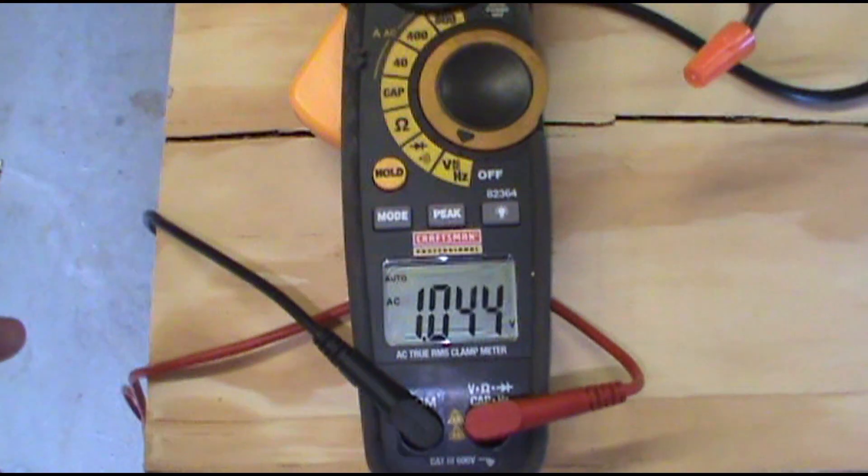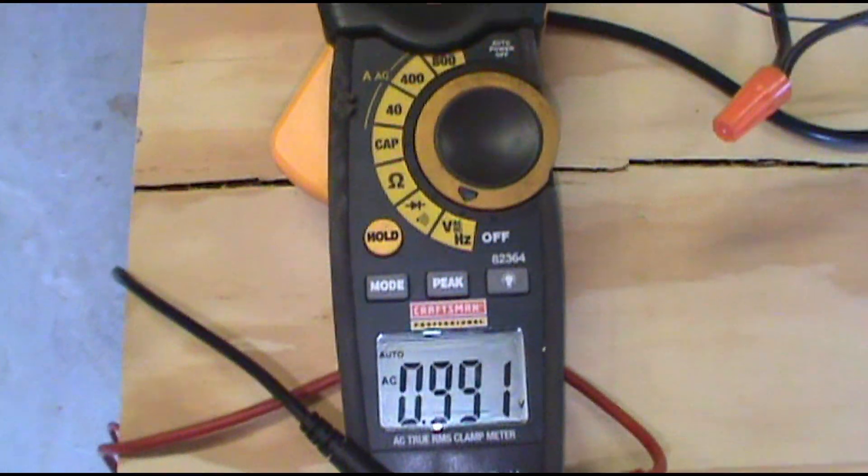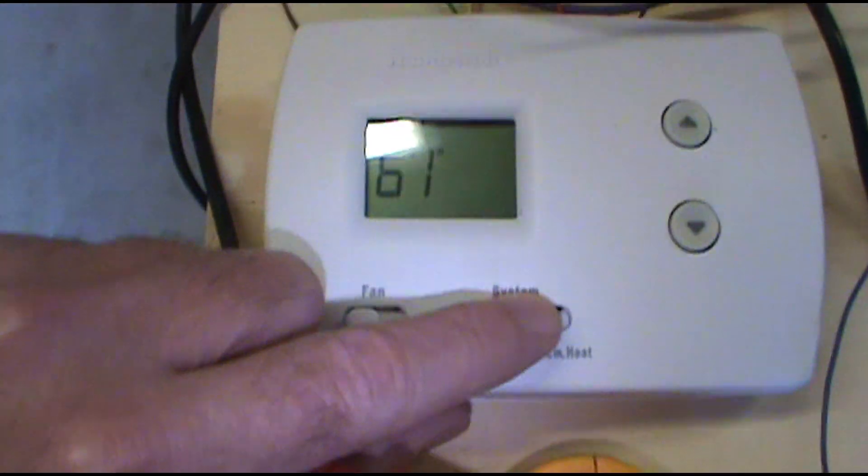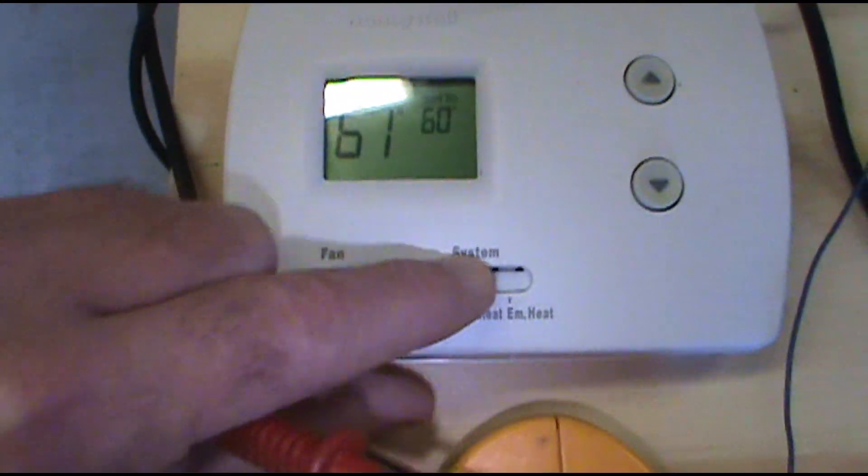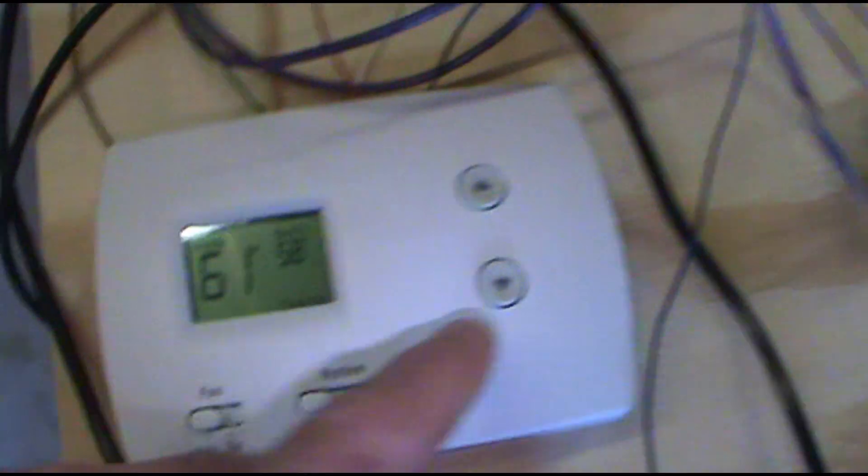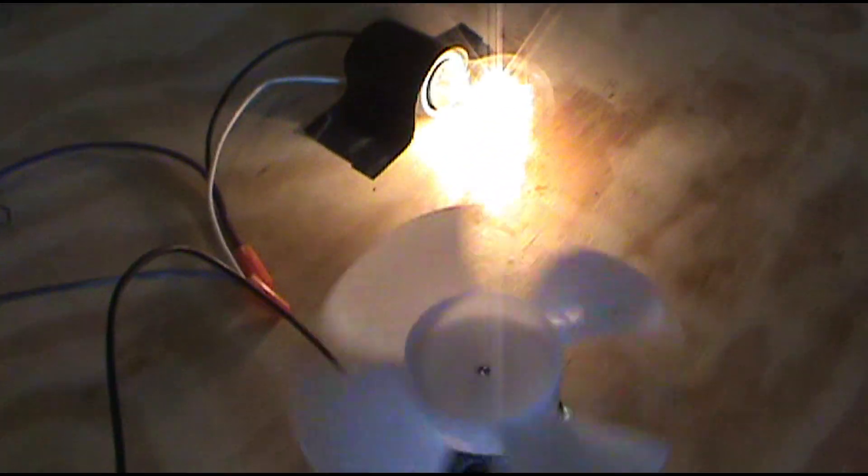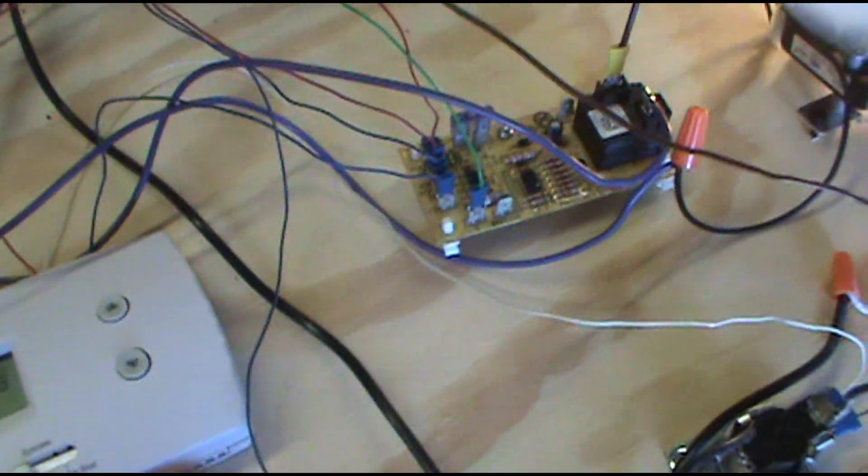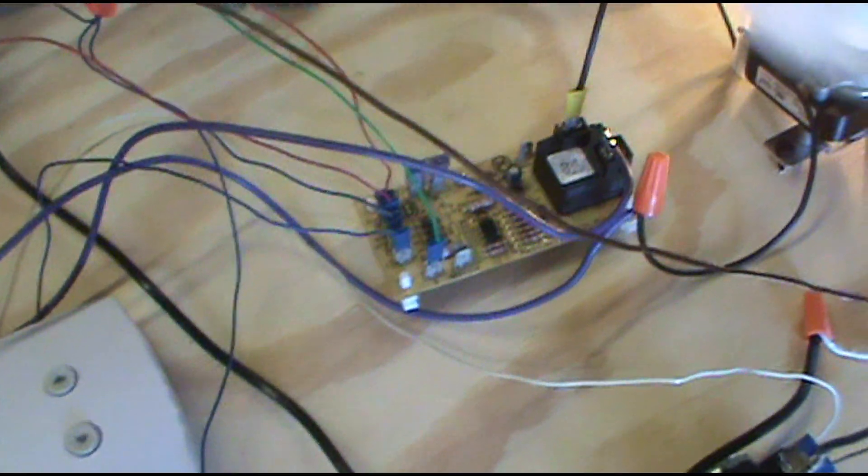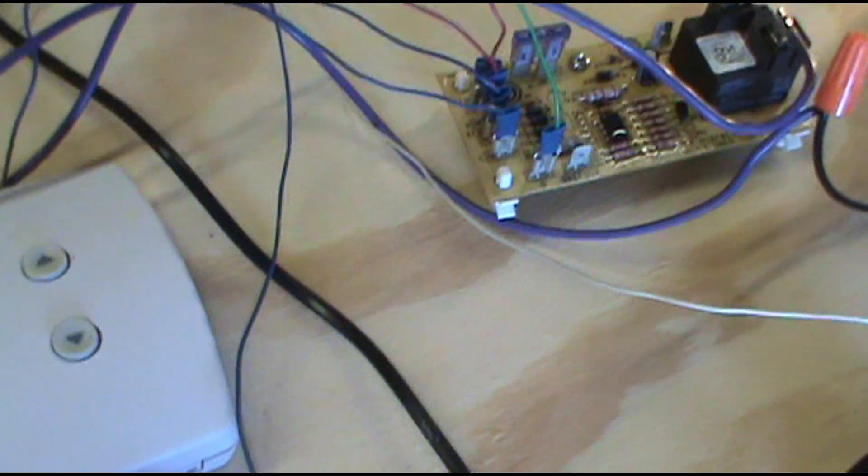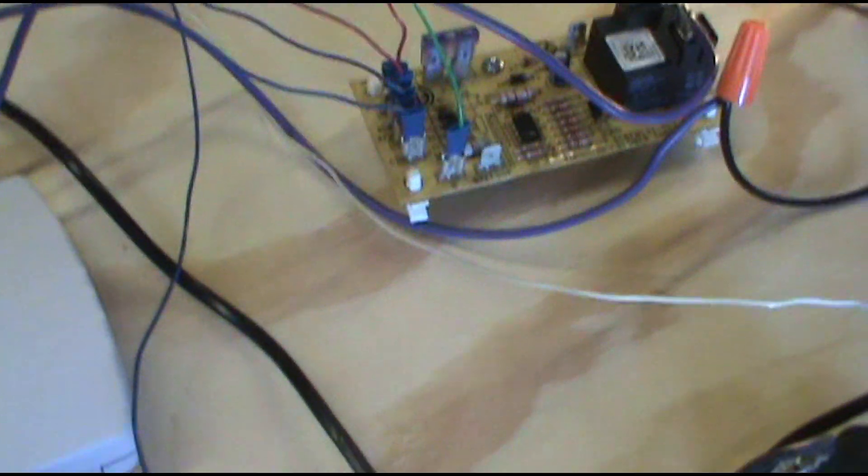Let's turn it off and play around with the old blower board here. Let's do some blower board scenarios, troubleshooting, just farting around. Set it down on cool, condenser's on, indoor fan motor is on. Let's say that the indoor fan isn't coming on. I know it's on here but we're just going to do a hypothesis here. Indoor fan ain't coming on.